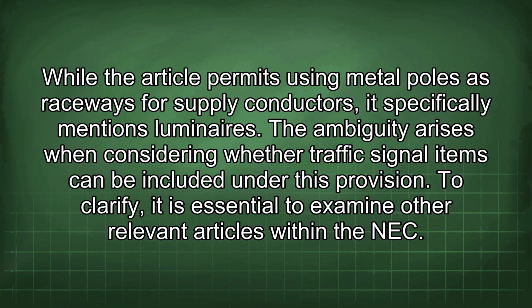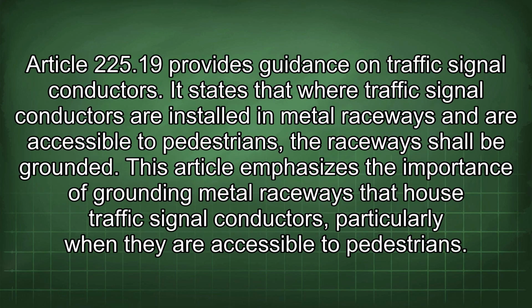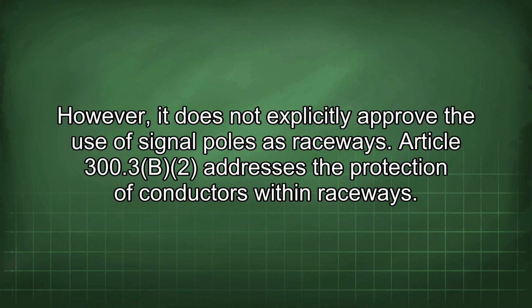To clarify, it is essential to examine other relevant articles within the NEC. Article 225.19 provides guidance on traffic signal conductors. It states that where traffic signal conductors are installed in metal raceways and are accessible to pedestrians, the raceways shall be grounded. This article emphasizes the importance of grounding metal raceways that house traffic signal conductors, particularly when they are accessible to pedestrians. However, it does not explicitly approve the use of signal poles as raceways.